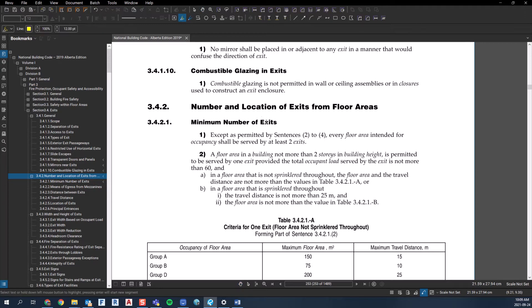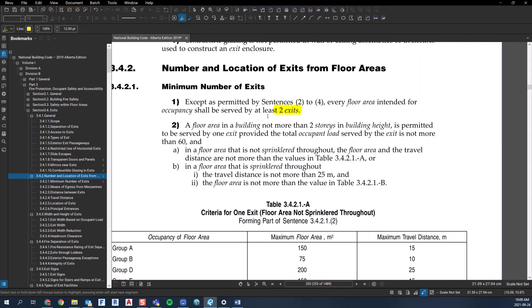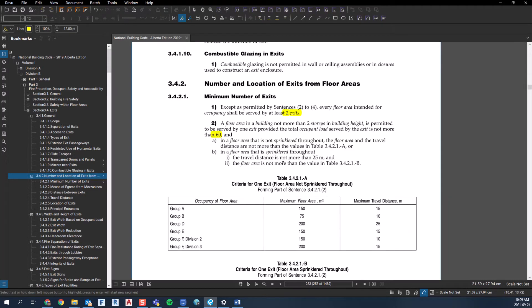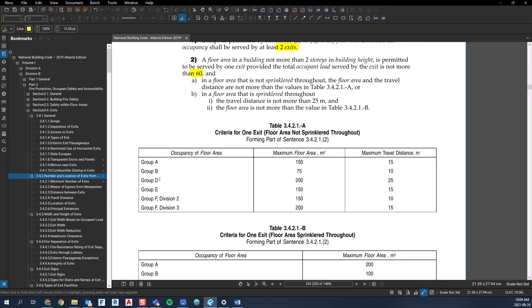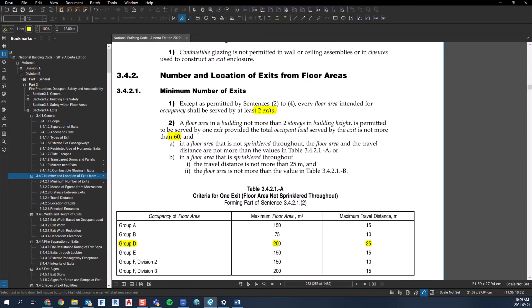So right away it's telling you you need two exits. The next sentence gets into situations where you can do one exit if you meet certain requirements. Some of those requirements are: you can't have more than 60 people in that floor area, depending on whether you're sprinklered or non-sprinklered there are maximum room sizes, it's based on the use of the floor area, and there are travel distances to the exit.